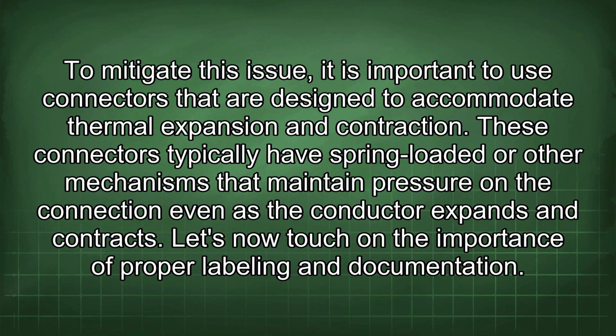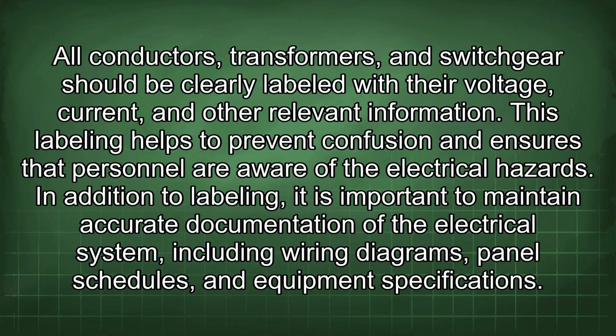To mitigate this issue, it is important to use connectors that are designed to accommodate thermal expansion and contraction. These connectors typically have spring-loaded or other mechanisms that maintain pressure on the connection even as the conductor expands and contracts. Let's now touch on the importance of proper labeling and documentation. All conductors, transformers, and switchgear should be clearly labeled with their voltage, current, and other relevant information. This labeling helps to prevent confusion and ensures that personnel are aware of the electrical hazards.